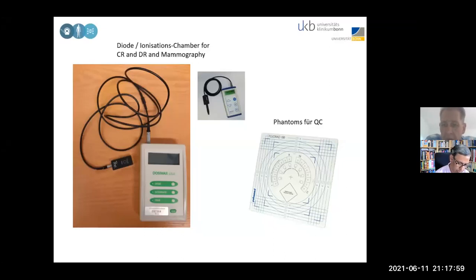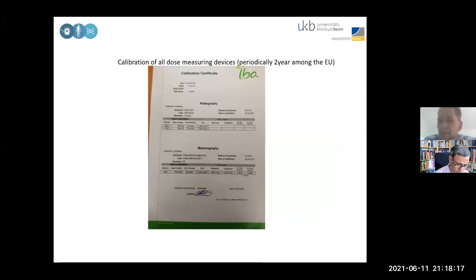They are usually divided up in different steps and contrast. I mean, we will come to this later. I only would like to show you that those diodes need to have a very important part: they need to be calibrated. And you have to check whether your devices are calibrated in the right manner. That means, are they calibrated for the energy you use? For example, if you use an ion chamber or a diode for an energy which they are not actually dedicated to, you may have problems.